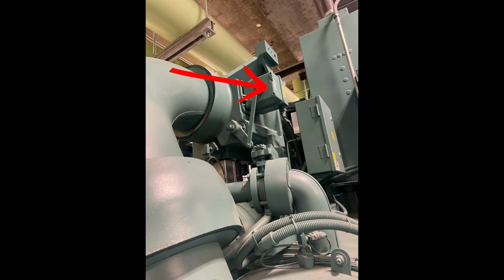Okay, so we've made sure that our actuator is at a fully closed position, our closed relay output is triggered, and that we've manually pressed the shaft for the PRV in this case to a fully closed state. By that time, that's when we can install our linkages.